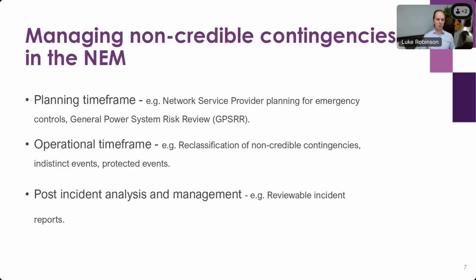And then the final one there in the operational time frame, which links to the risk review, is protected events. If we've, prior to the operational time frame, declared a protected event, then in the operational time frame we can take measures to operate the power system to improve its resilience. Similar measures to the other 2 in the operational time frame. It generally means we would be constraining flows on corridors or cut sets in the power system. And then the third element I wanted to touch on in terms of how we go about managing these major events is that we have quite detailed processes and quite clear obligations to investigate and report on major events that occur. And so we will undertake a detailed review of events which are considered to be of significance to the operation of the NEM.